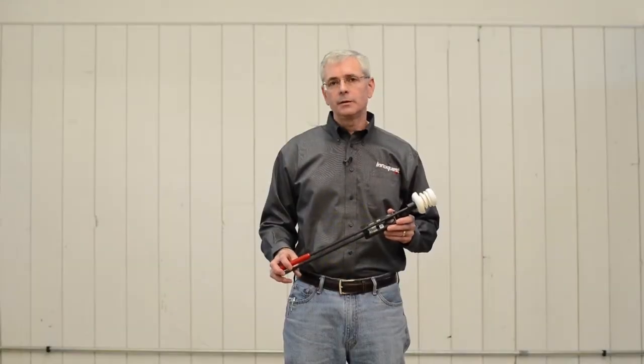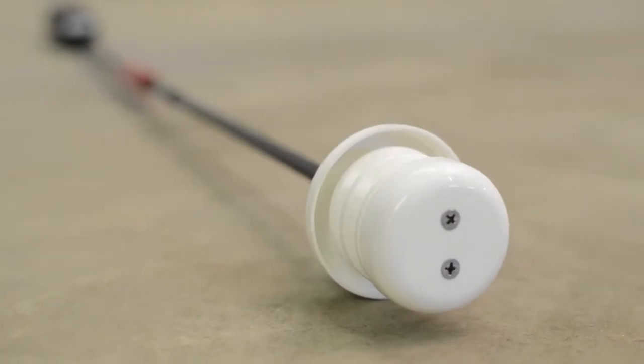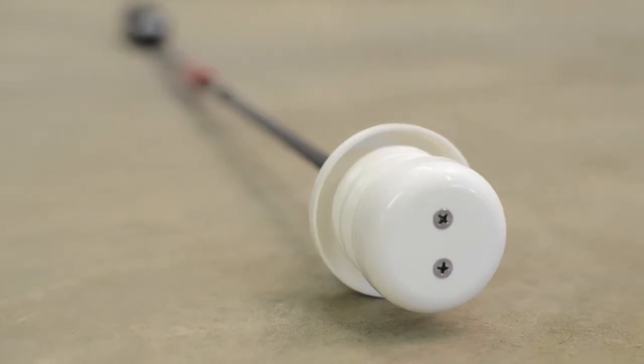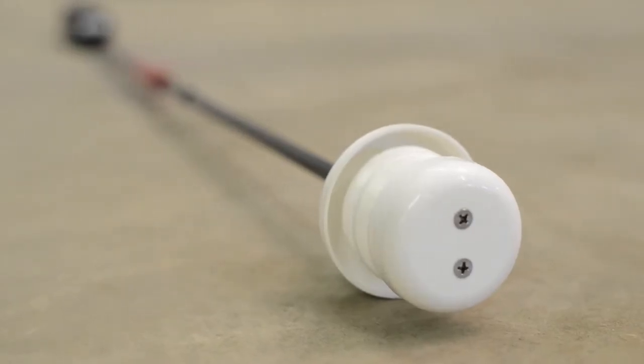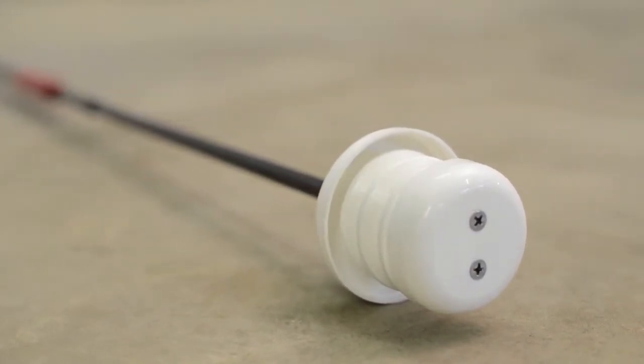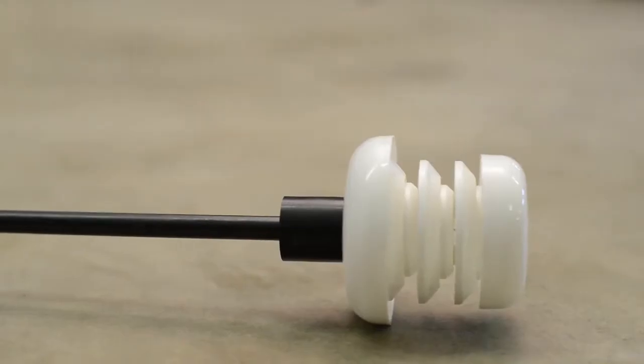Our meter follows the North Dakota State University protocol for determining inversions, similar to their NDAWN weather station network. Our meter has several key features I'd like to show you. We have a high accuracy temperature sensor and we provide a NIST traceable certificate to you. The temperature sensor is surrounded by radiation shields which protect against errors from sunlight or other sources of heat radiation.